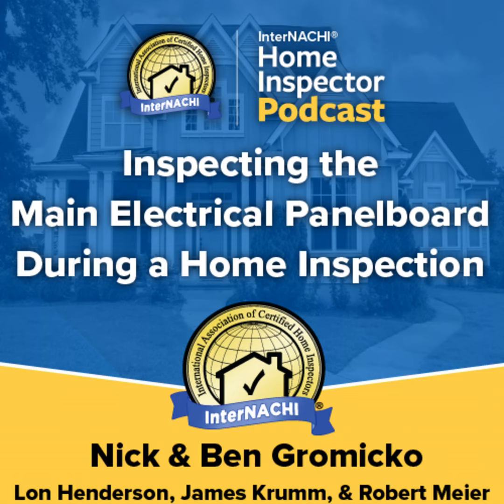Home inspectors may receive criticism from unhappy sellers and even from some electricians about the need to replace these panels. Two common arguments against replacement are, "It's working just fine," or "the old breakers can be replaced with new aftermarket breakers." No one can know if it's working just fine until it's under stress. One of the significant issues with FPE, Zinsco, and Bulldog panels is that the breakers fail to trip with overcurrent, shorts, or ground faults at rates far higher than industry standards. In actual testing, breakers in these panels may trip correctly a few times before failing.